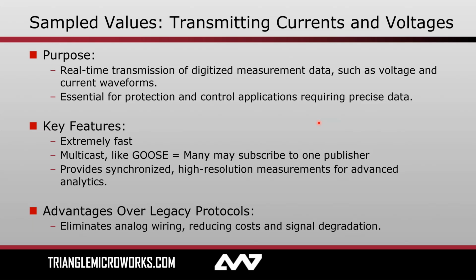Much like GOOSE, it's going to be extremely fast and it's also going to be multicast, meaning that you can have many subscribers, but just one publisher. There's a key difference here. Well, several. One, it's not event driven. The data is constantly changing as the waveform is fluctuating up and down multiple times per second. And anytime a sample is taken, that's when a new message is going to be published.